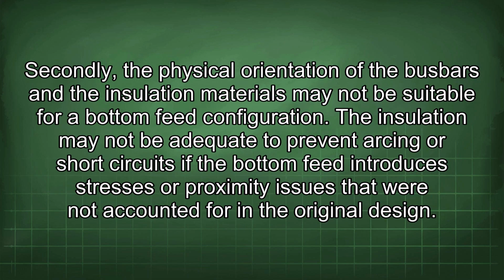Secondly, the physical orientation of the busbars and the insulation materials may not be suitable for a bottom feed configuration. The insulation may not be adequate to prevent arcing or short circuits if the bottom feed introduces stresses or proximity issues that were not accounted for in the original design.